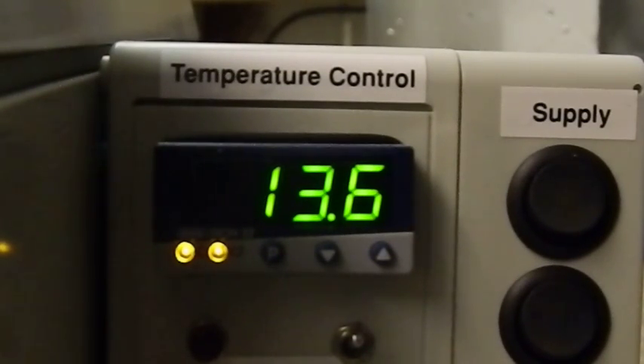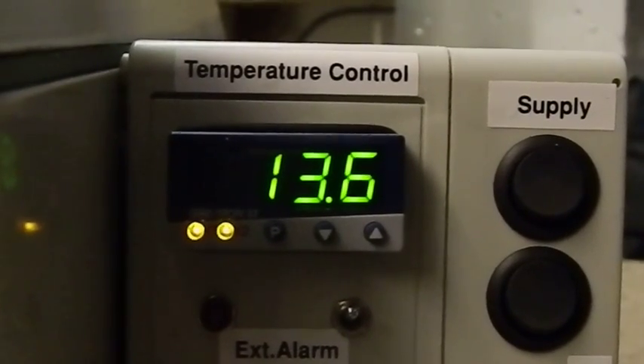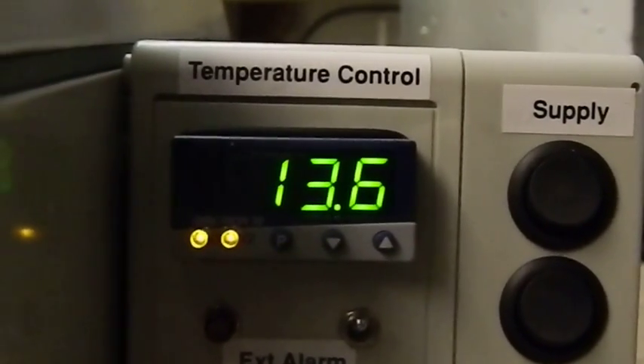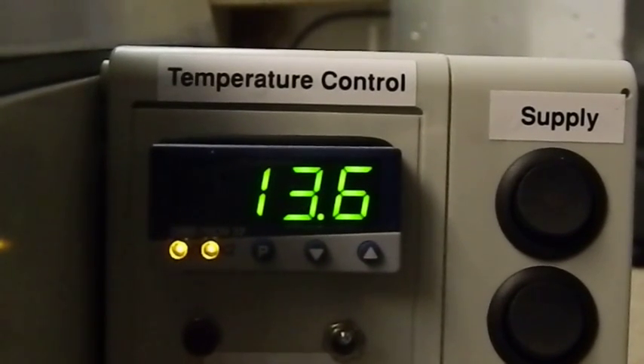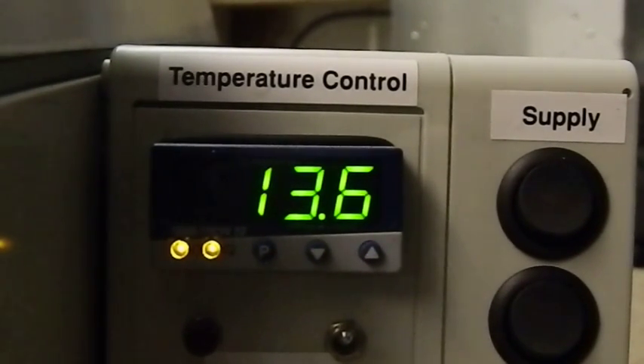Okay, the first thing you need to do is to understand that the processor has no known reference point in its memory, so you need to give it a reference point as to what the temperature actually is. Now, to be sure of what the temperature actually is, we use inside the machine a calibrated mercury thermometer. This particular one comes from a Scientific Suppliers, and they put it through their own test house, and it's calibrated at 37.5 with a variation of 0.05 degrees, so it's five hundredths of a degree variation, which is plenty adequate for this job.